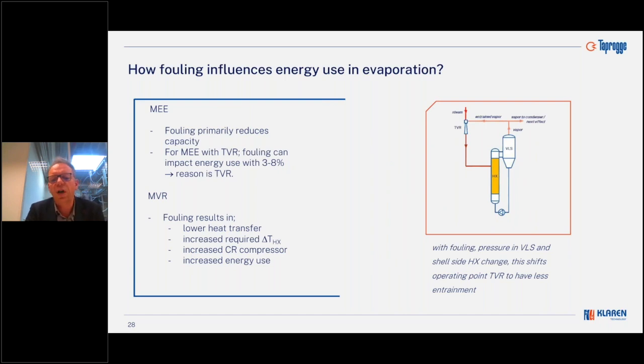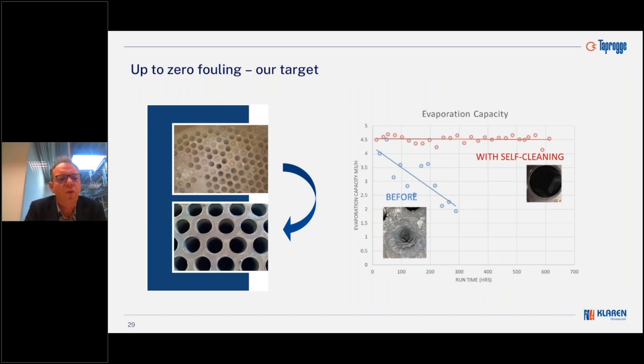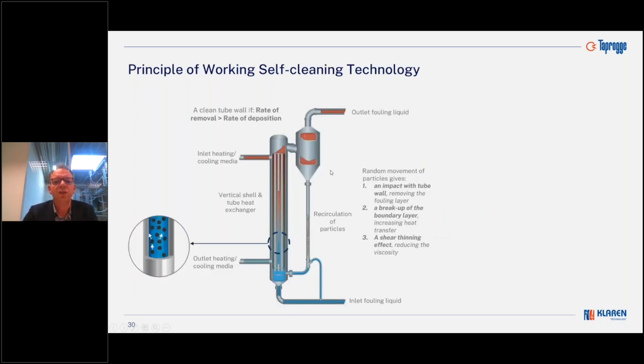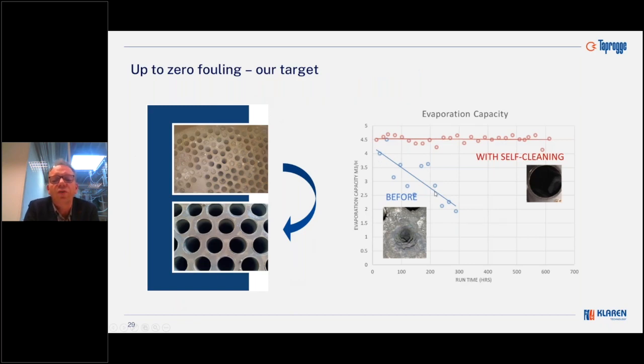So what is our target? The target with the KLAREN technology, in fact, is to avoid this fouling, to make sure that the heat exchanger remains clean. So what you see is that we start with clients that have a problem, with the picture at the top left: dirty tubes, some of the tubes clogged. After a change, when we open the heat exchanger, and that's when the picture was taken, you still see shiny tubes. And the shiny tubes have an optimal heat transfer coefficient. So if you talk about evaporation capacity, we go from a straight declining line with the blue dots, as in the previous slide, to the constant line with the red circles, where there's a constant evaporation capacity.